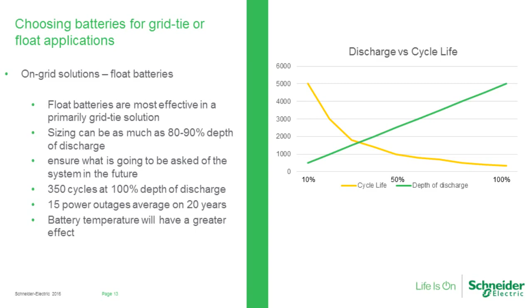One thing that's worth noting within the research that I did for this presentation is that battery temperature actually had a huge relationship with how those batteries survive. Even float life batteries can have a shortened life if the batteries aren't kept at about 20 degrees C or lower. Anything higher than that, and we start affecting the battery's overall life as well. So when designing a system, think about putting it in a place where it is fairly temperature controlled. An outdoor garage that gets up to 90 degrees in the wintertime or in the summertime may be a little too warm a place for those batteries. You may need to look elsewhere or figure out a different way of storing those batteries.